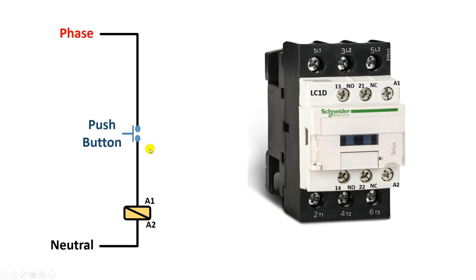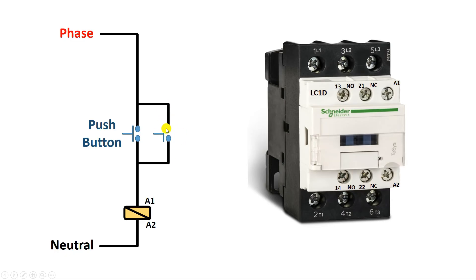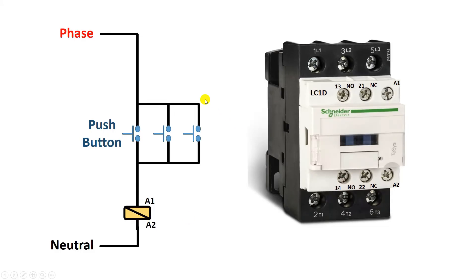If you want to turn on the contactor from two places — one push button here, by pressing this you can turn on the contactor, and you have one more push button by which you also want to turn on the contactor — then how to do the wiring. If you want to turn on the contactor from different places, with the first push button connect another push button in parallel. From the upper terminal, provide input power supply to this push button, and connect a wire from its output terminal to the output terminal of the first push button. Overall, connect another push button in parallel to the first. By doing this, phase supply will be at both input points. Press any one of the two push buttons and the power supply will go to the contactor and it will be turned on. For one more push button, connect it in parallel in the same way.